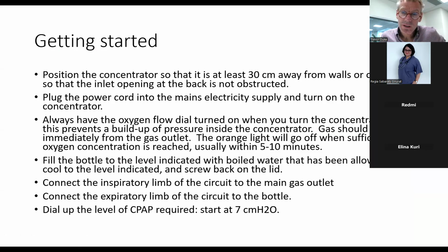So I just wanted to go back a step and say how to get started with a CPAP machine. And the first thing is just standard things. You need to position the concentrator so that it's about a foot or 30 centimeters away from walls, and keep it out of the direct sunlight. You want it away from walls or curtains so that the gas can flow into the machine. It's the standard way we look after an oxygen concentrator.